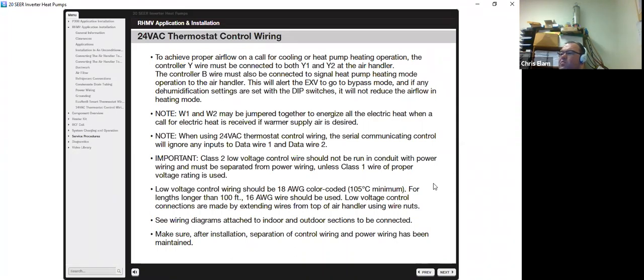When using a 24-volt controller, the serial communicating control will ignore any inputs to data wire 1 and data wire 2. Class 2 low voltage wiring should not be run in conduit with power wire because it will interfere with communication.